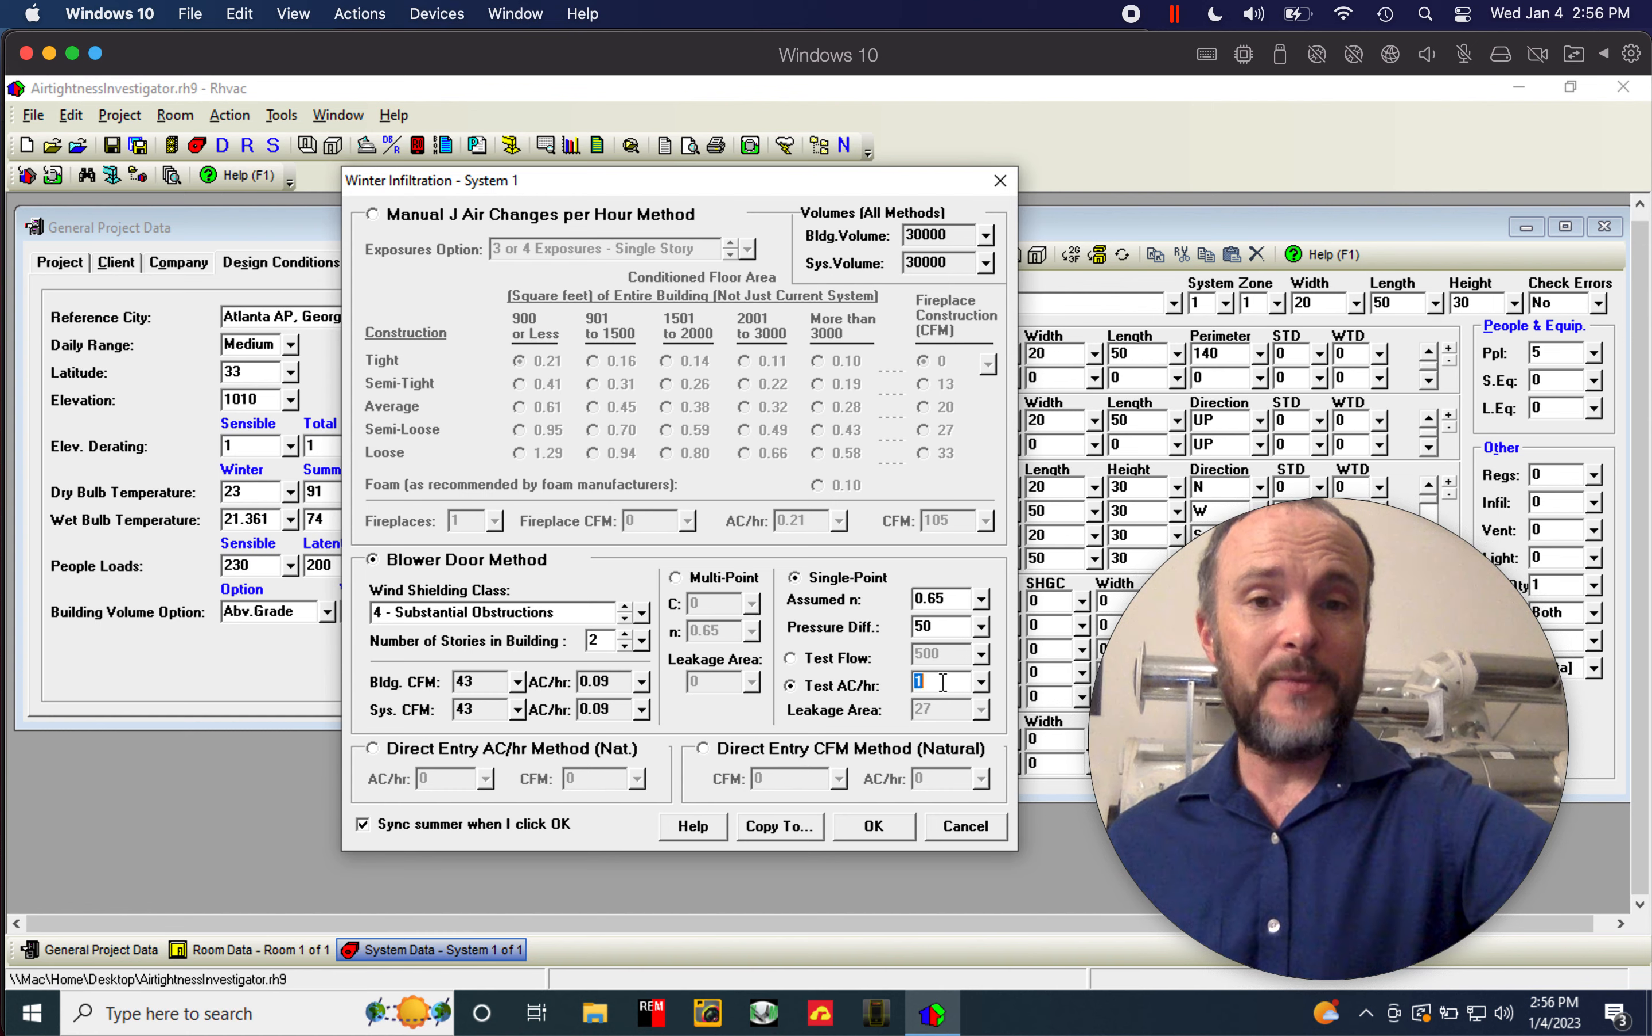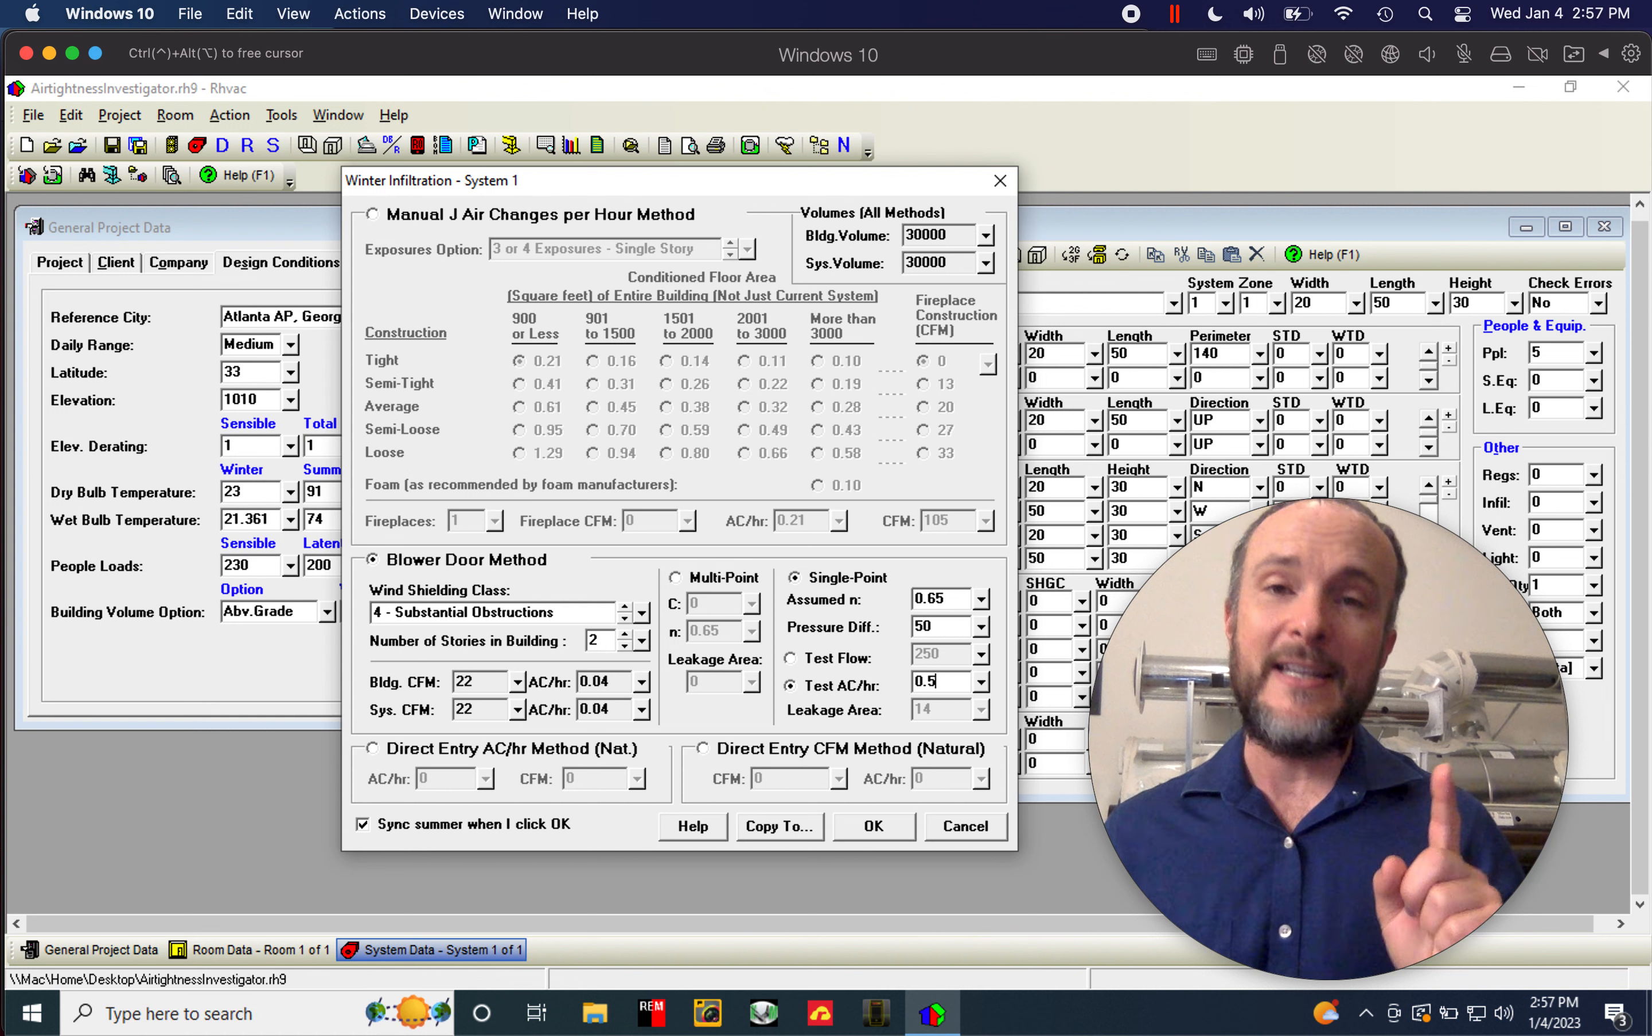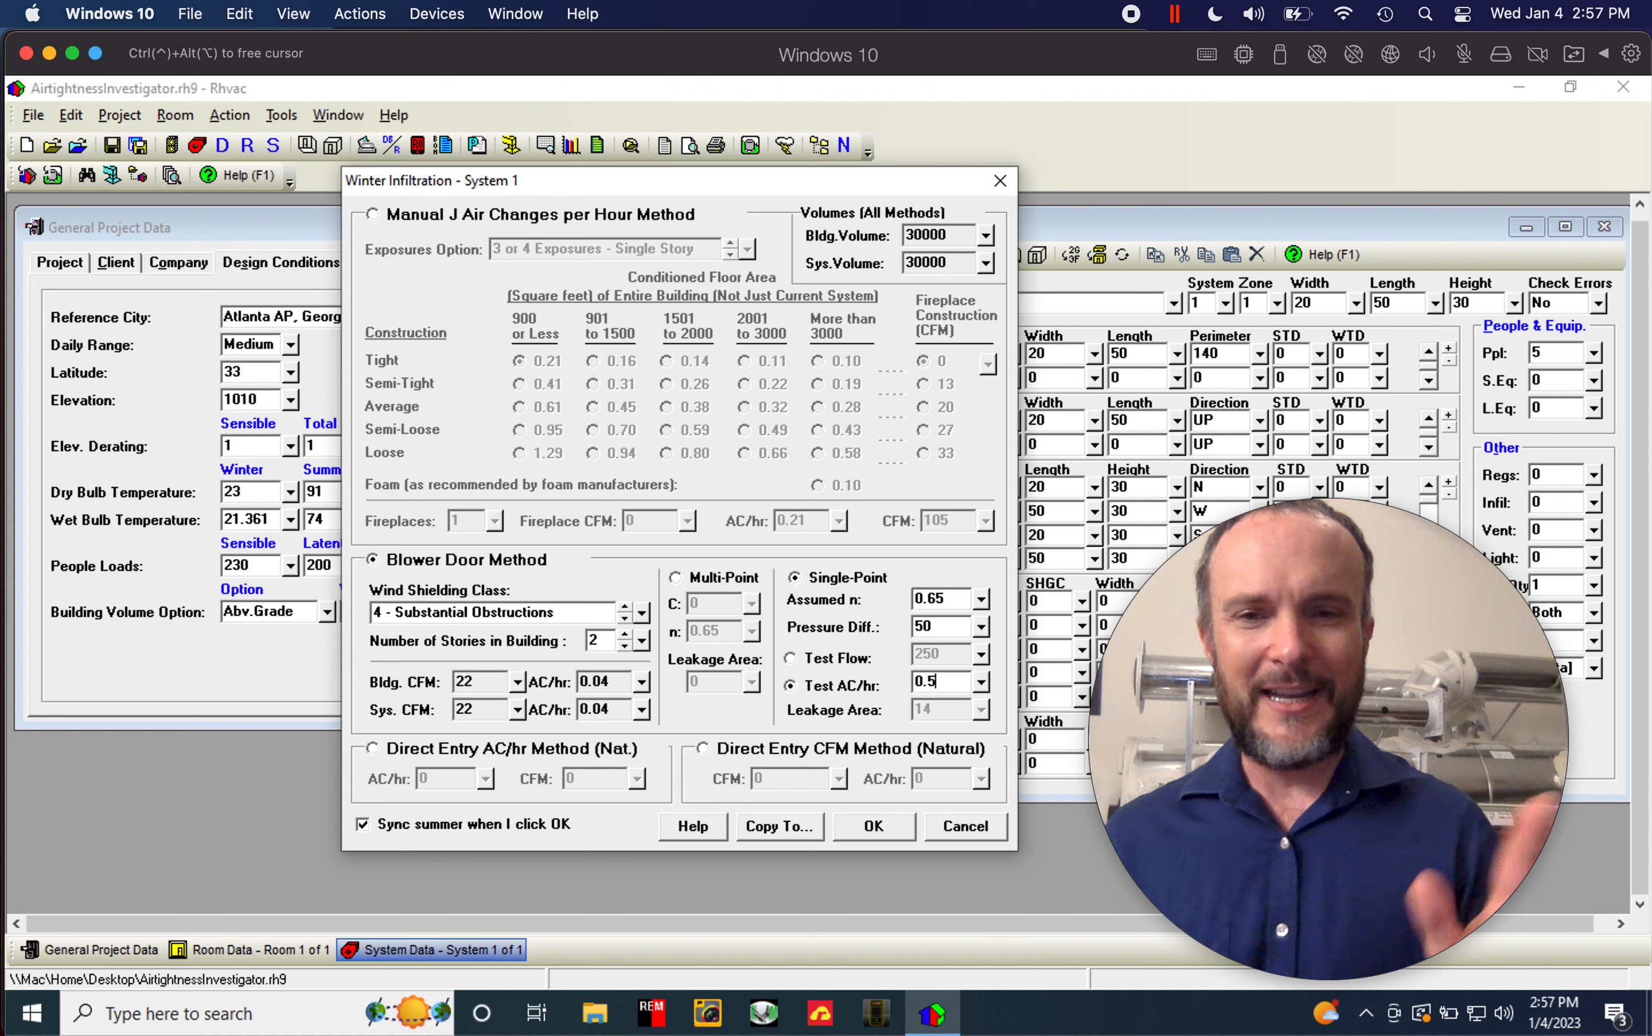And if they're insane, meaning like me, then 0.5 might be something you would do, but you want to be conservative about this. And once you get past like two, the point of diminishing returns is already kind of kicked into place. So you're not going to get massively different sizing by going south of one, which might be why this is like that on the defaults. They might think, oh, it just doesn't matter once you get that tight, which is kind of true. But honestly, I think that it does make a big difference because we're also in very tight homes going to be adding ventilation. And that is going to kick up the latent load, the humidity that's being added to the house in the summertime and all the sensible stuff, the heat bleed that's happening in the wintertime and the summertime. And if we're doing that, we want to minimize, we want to actually put in the exact number that we can on the infiltration because that air leakage is going to hurt us. And then some with the ventilation, sorry to get really into the weeds with that, but the substantial obstructions piece is another piece of this.